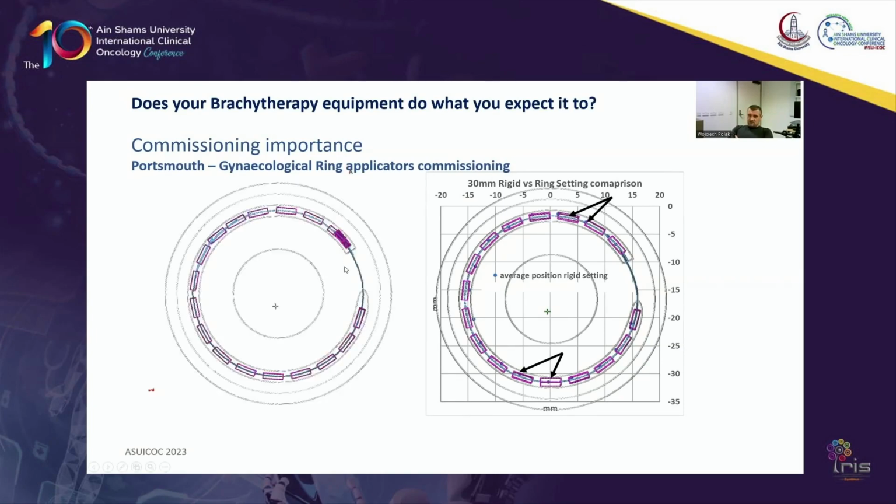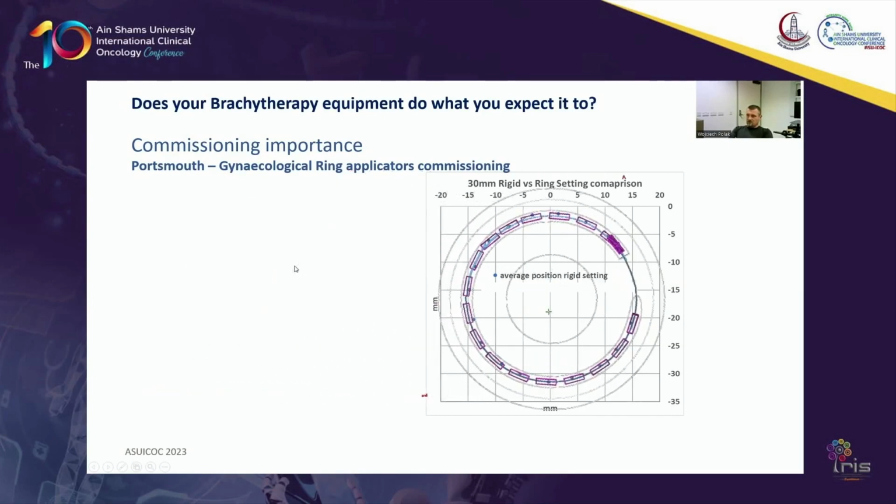The manufacturers allowed us to adjust that path, and that's what we've done within the treatment planning software. However, you cannot save that in the solid model library, so there's another complication. We have to create template plans and use the template plans for our treatments. So you can see that we squeezed the source positions in our new model. And when we overlay the new model over the source measurements, you can see that they correspond to each other quite well. So we managed to reduce the error of the source position to less than 1 millimeter, and that was quite consistent with the repeated measurements.